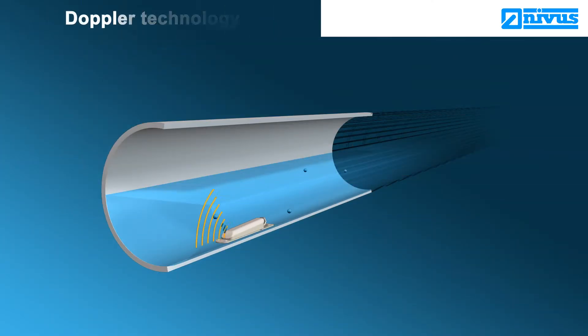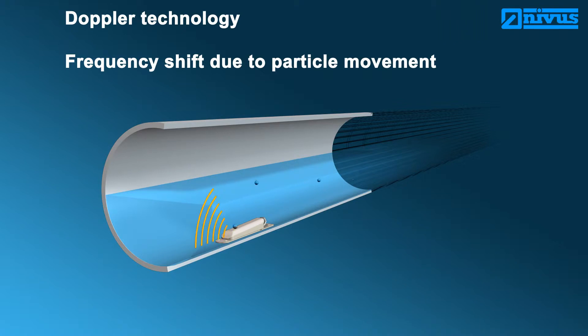Flow measurement using Doppler systems. The Doppler technology uses a sensor continuously transmitting ultrasonic signals at a constant frequency. The particles contained in the medium reflect the signal. The particle movement shifts the frequency of the reflected signal.